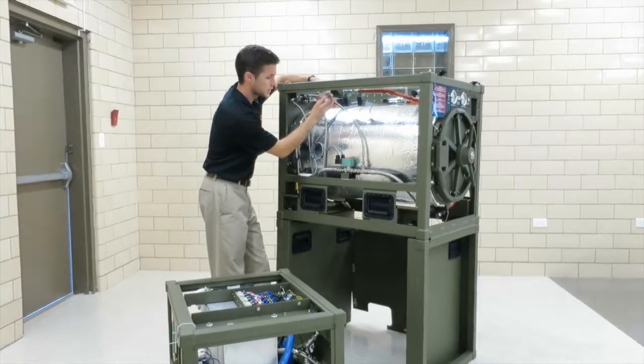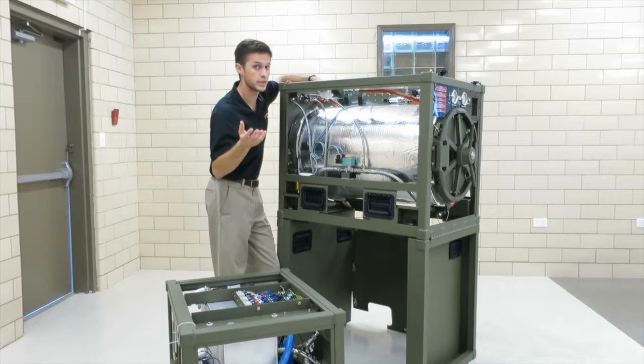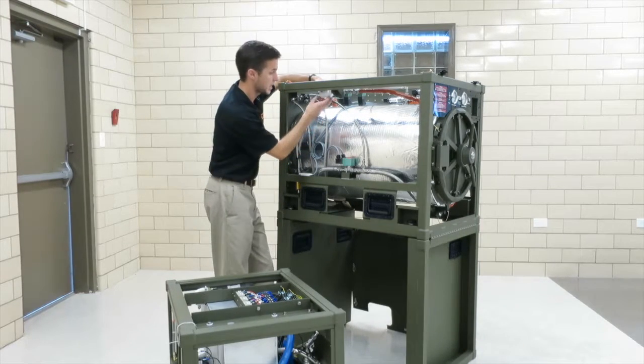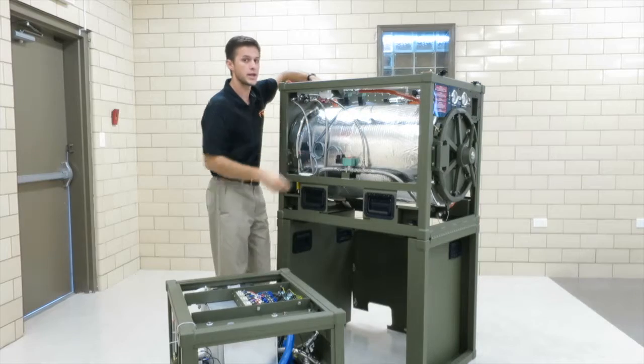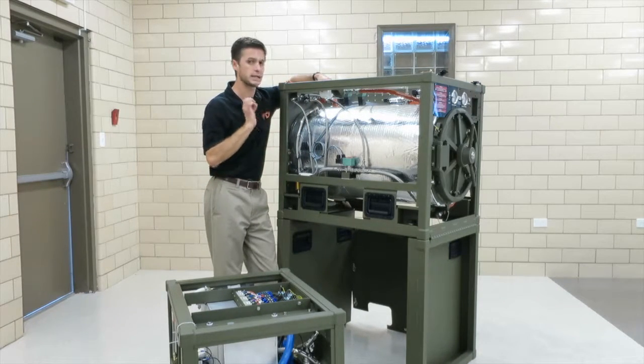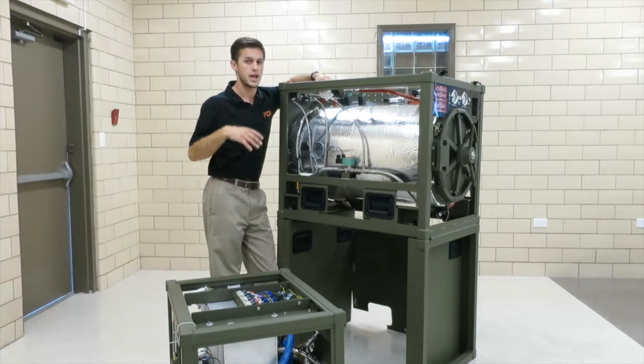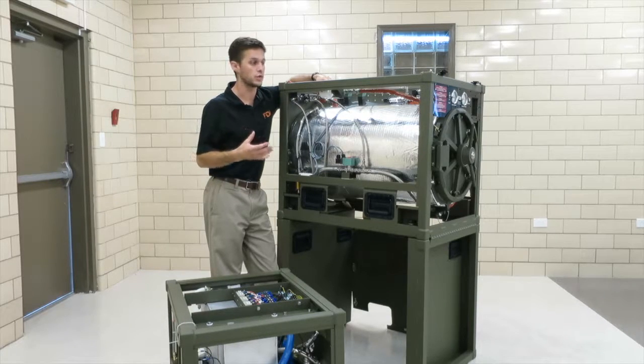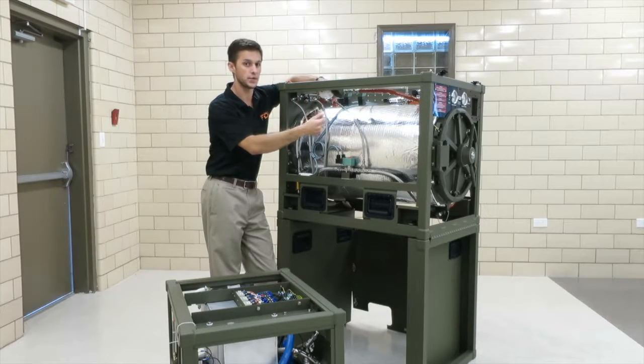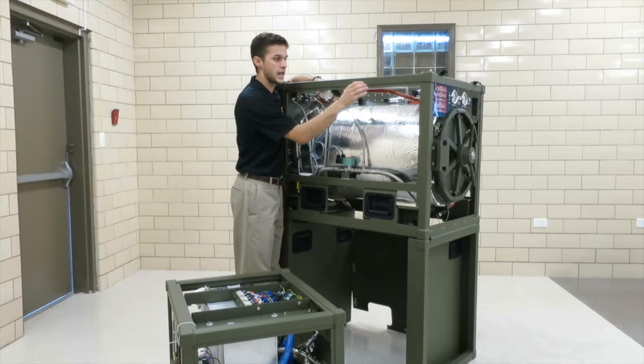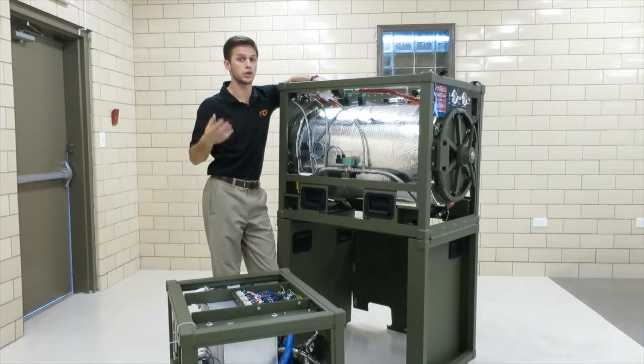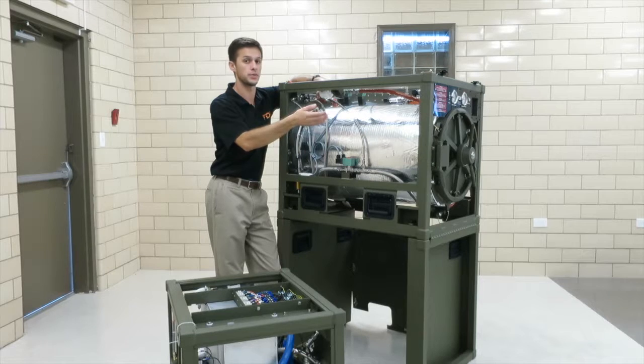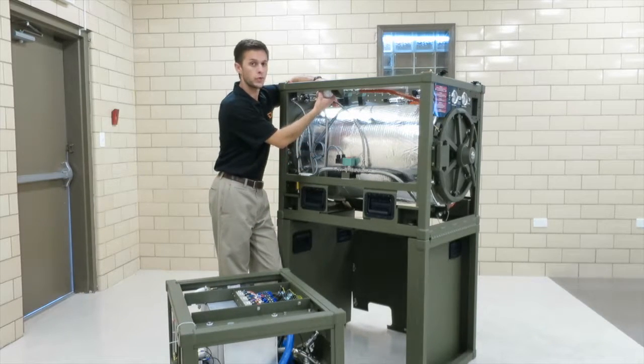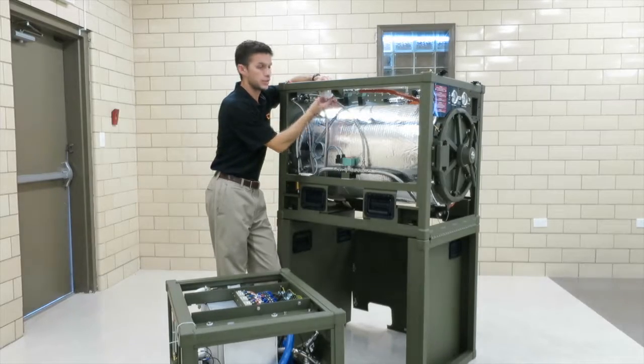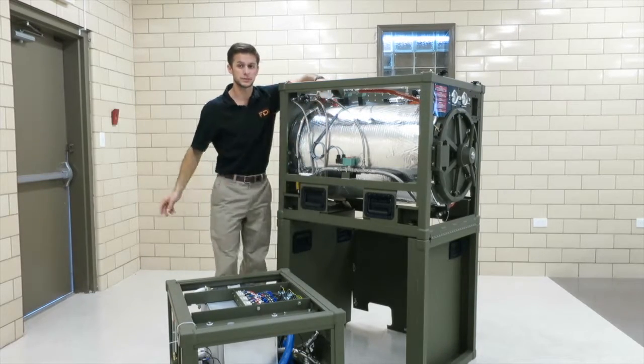So when you replace this HEPA filter, which we'll have another video on how to replace, you're ensuring that clean air is going to hit the instruments at the end of the cycle. At the end of a cycle, if there's a vacuum in the chamber, it's going to draw outside air into the chamber to neutralize the pressure so the user can open the door. So it's very important that we have clean air hitting the instruments. So this is supposed to be replaced every 6 months.